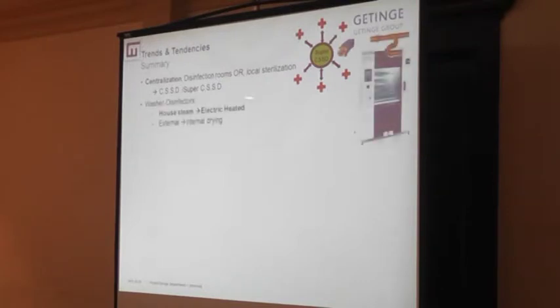The washers, we go to electric heat washers. I heard today that it's very common here in South America that we mostly use electric heat, not house steam. And that is for sure the trend in Europe as well. But that gives a 10 to 20% longer process time. And internal drying in the washer is highly recommended, so we don't recontaminate the wet goods when we take them out from the packing area.